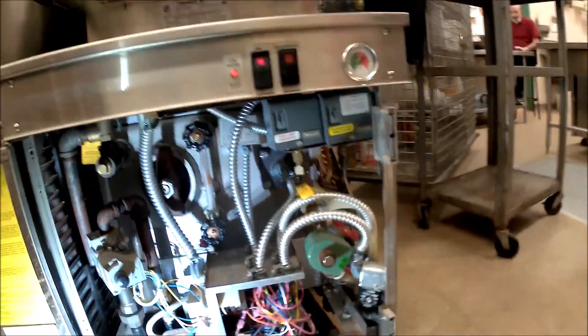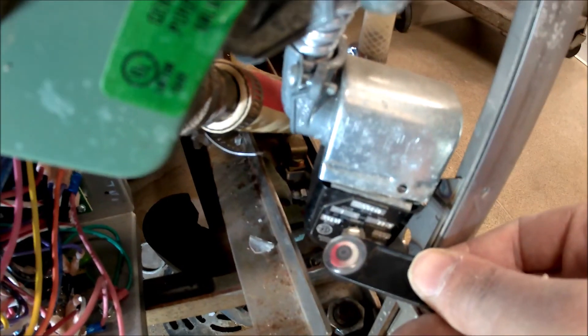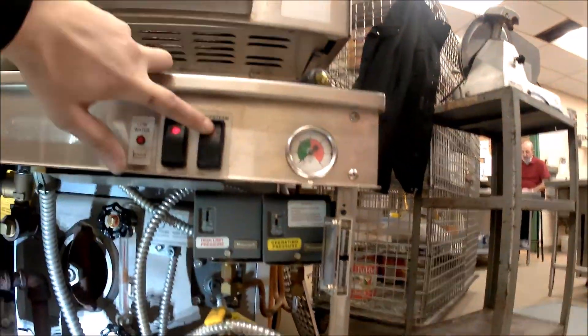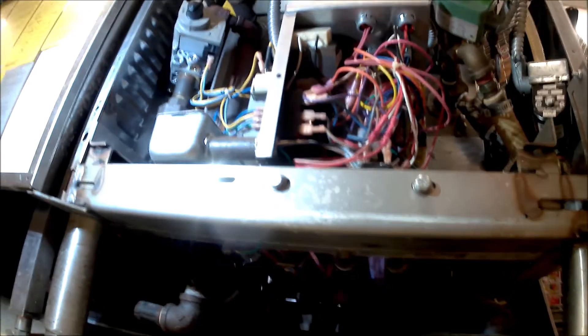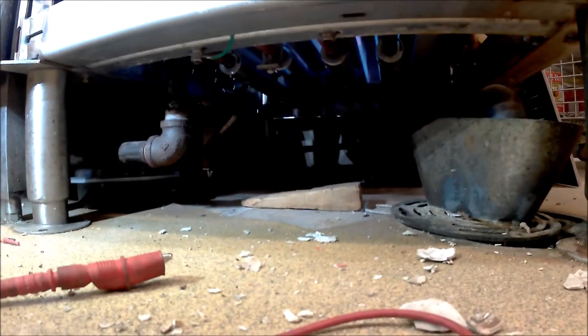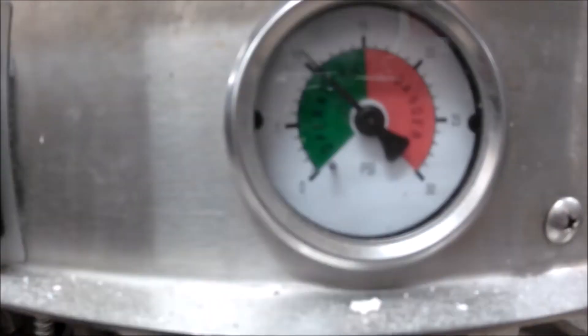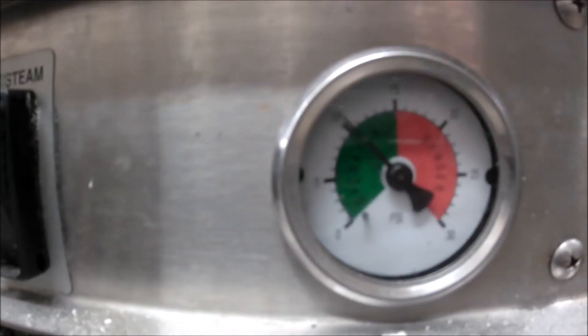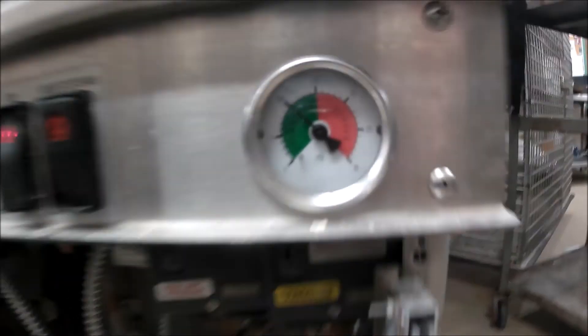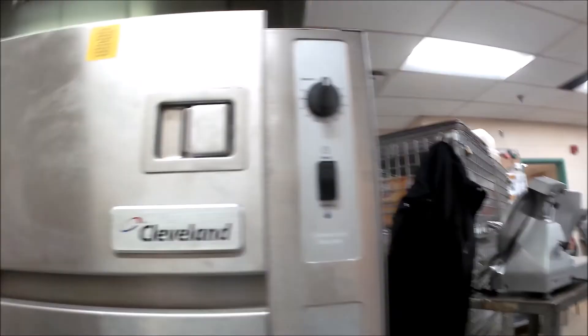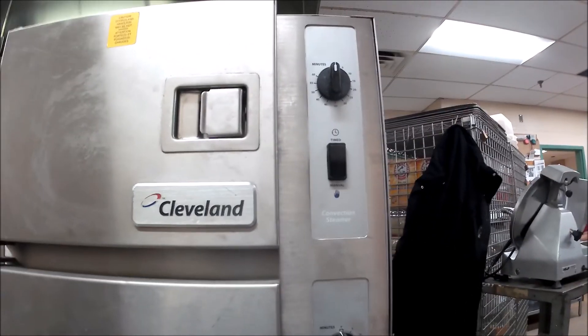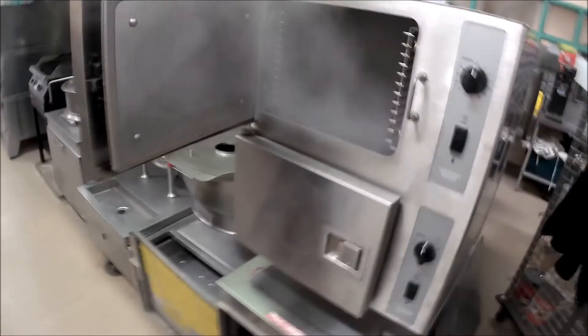We're back on, we're filling the boiler, filled up. The burner is turning on, that's good news. Last thing I'm going to test now is test the pressure - we cut off around nine psi. Let's just go confirm we're getting steam up into our steam cabinet here. We have tons of steam, we are all good here.